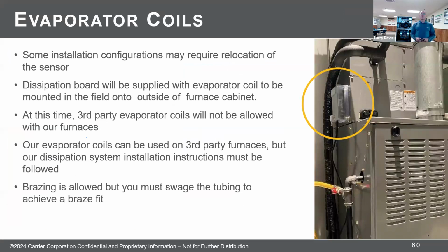Dissipation board for a furnace fan coil, it comes with the furnace and evaporator coil. Dissipation board comes with the indoor coil, not the furnace. So you'll see it here. You can use this, a 454B system, on any furnace, as long as you wire that in to the control, as you'll see in the instructions. Does the dissipation board come with a wire harness? Wire harness is provided.